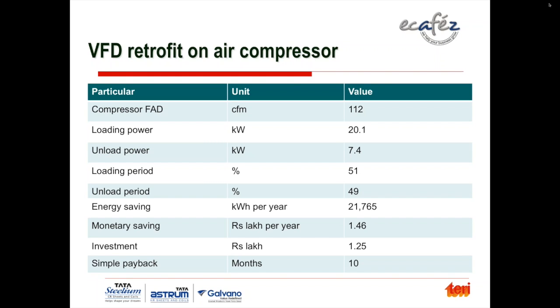Energy saving in units per year is 21,765 units of electricity, and it essentially leads to monetary saving of 1.46 lakhs per year. Investment on the VFD is 1.25 lakhs, and the payback is just 10 months. A very attractive option. But here a word of caution about VFD retrofit. It cannot be done for all air compressors. So you have to consult your air compressor manufacturer. Essentially, these are for screw air compressors only.